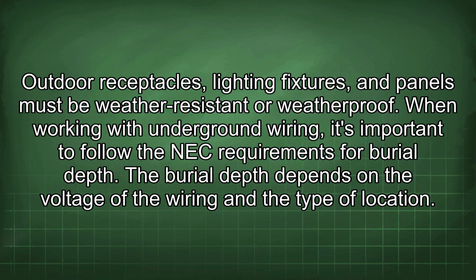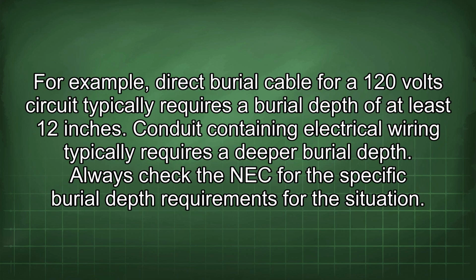When working with underground wiring, it's important to follow the NEC requirements for burial depth. The burial depth depends on the voltage of the wiring and the type of location. For example, direct burial cable for a 120-volt circuit typically requires a burial depth of at least 12 inches. Conduit containing electrical wiring typically requires a deeper burial depth. Always check the NEC for the specific burial depth requirements for the situation.